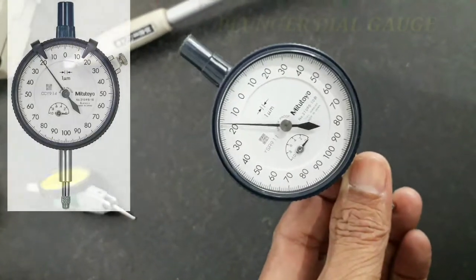Today we are going to discuss dial gauges - plunger dial gauges or dial indicators, lever dial gauges - and how they are calibrated using a universal measuring machine. It's a metroscope, shortly called ULM. The least count of ULM is 0.1 micron. It's a very accurate machine, used for calibrating dial gauges, especially plunger dial gauge, lever dial gauge, bore dial gauge, and thread and plug gauges, etc. There are various types of dial gauges used for measuring small linear deviations.